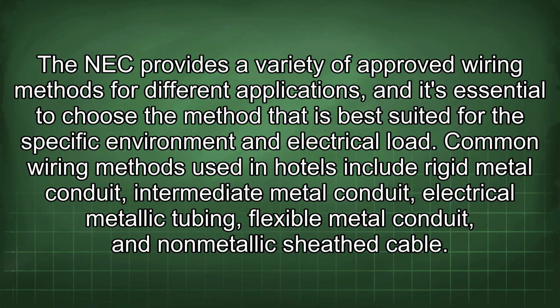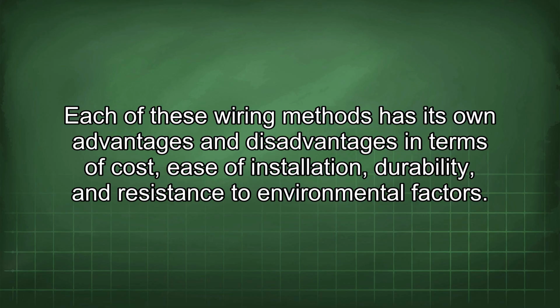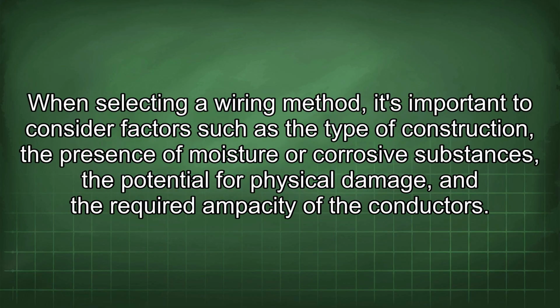Common wiring methods used in hotels include rigid metal conduit, intermediate metal conduit, electrical metallic tubing, flexible metal conduit, and non-metallic sheath cable. Each of these wiring methods has its own advantages and disadvantages in terms of cost, ease of installation, durability, and resistance to environmental factors. When selecting a wiring method, it's important to consider factors such as the type of construction, the presence of moisture or corrosive substances, the potential for physical damage, and the required ampacity of the conductors.